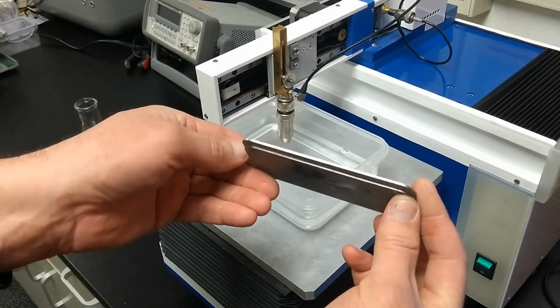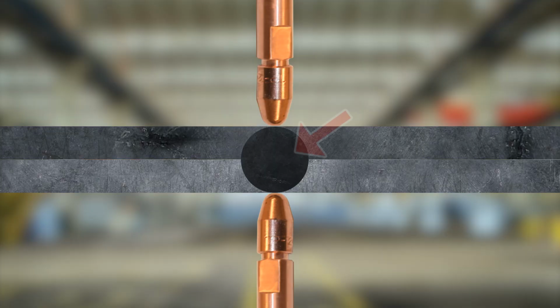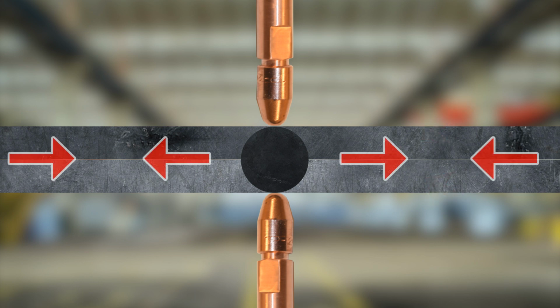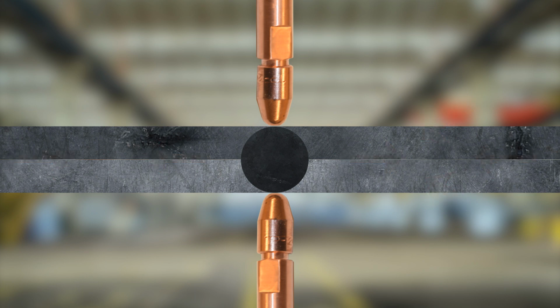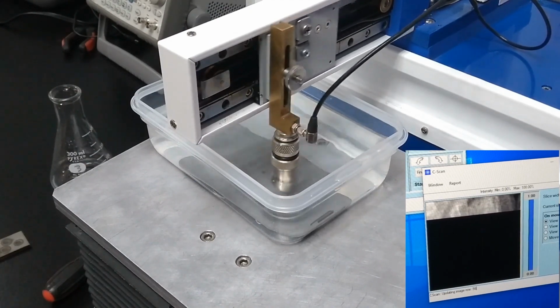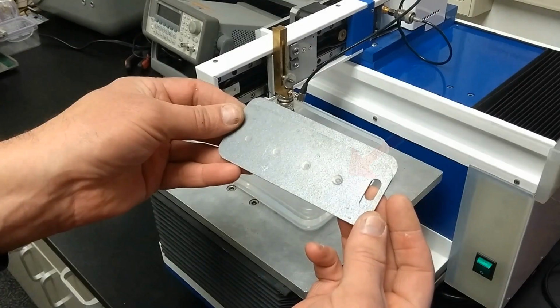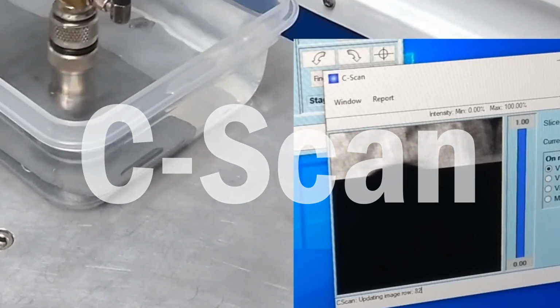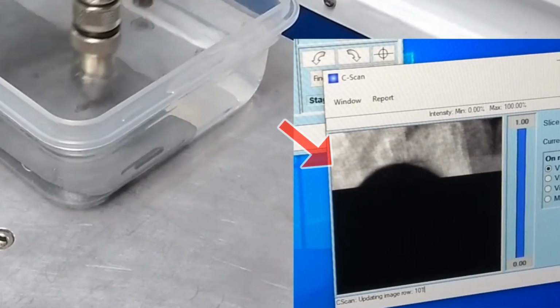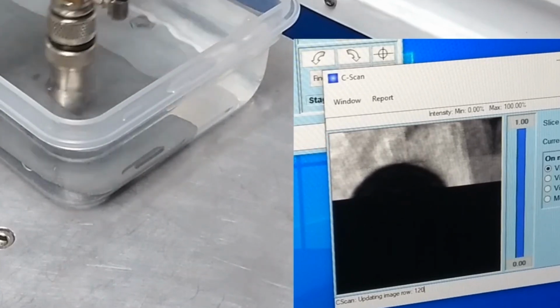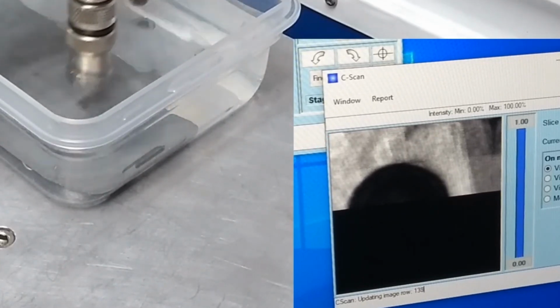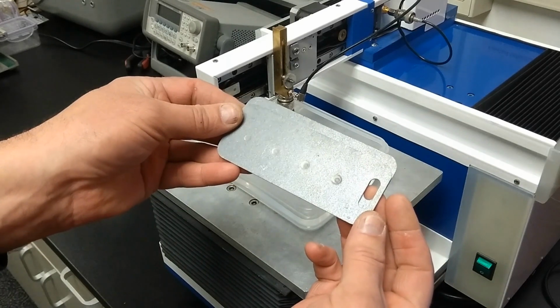Because this sample has areas of continuous metal, the spot weld nugget, as well as two plates separated by a gap, the unwelded area, the signal from the transducer will respond differently based on these two areas. On a B scan, we can expect to see horizontal lines, representing reflections. The fused nugget area should interrupt these lines. On a C scan, the software will compile an image of the sample. A dark black area will show the fused nugget, while lighter gray regions represent unfused areas.